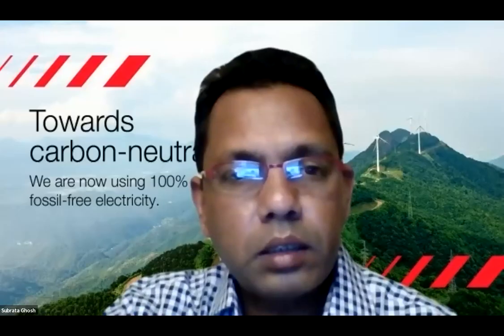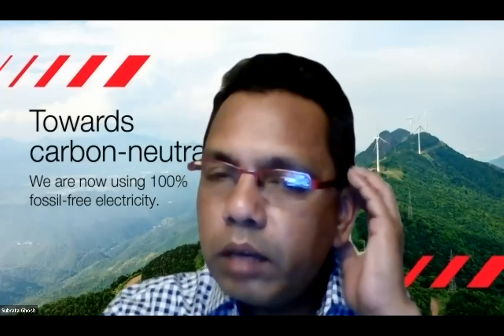Yes, so basically, as I said, the SFC controls the breakers: the incoming breaker from the 33 kV switchgear on the Northern Power Grid side, and also the incoming breaker on the 25 kV switchgear. So the IEDs on the incoming breakers are all talking to the SFC control system.